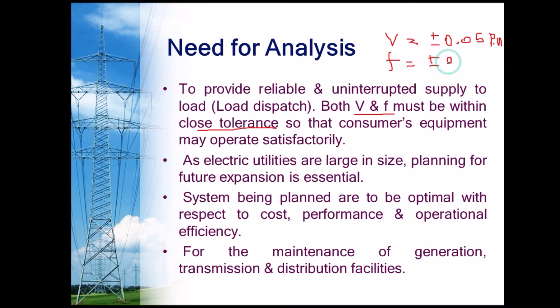The quality of power is determined by two factors: voltage (V) and frequency (F), which should be maintained within a close tolerance value. The voltage tolerance is plus or minus 0.05 per unit, and the frequency tolerance is plus or minus 0.5 hertz. In India, we use 50 hertz, so the allowed range is 49.5 to 50.5 hertz, though 49.5 is considered very low and we must maintain values within close tolerance.